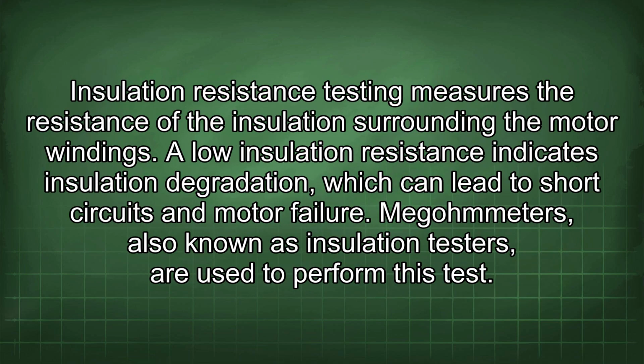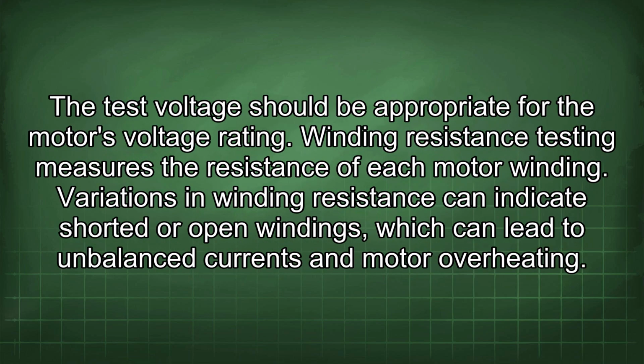Insulation resistance testing measures the resistance of the insulation surrounding the motor windings. A low insulation resistance indicates insulation degradation, which can lead to short circuits and motor failure. Megohmmeters, also known as insulation testers, are used to perform this test. The test voltage should be appropriate for the motor's voltage rating.